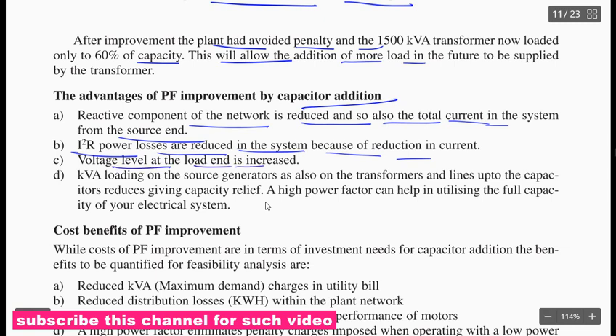Voltage level at the load end is increased. kVA loading on the source generator, as also on the transformer and lines up to the capacitor, is reduced, giving capacity relief. A high power factor can help in utilizing the full capacity of your electrical system.